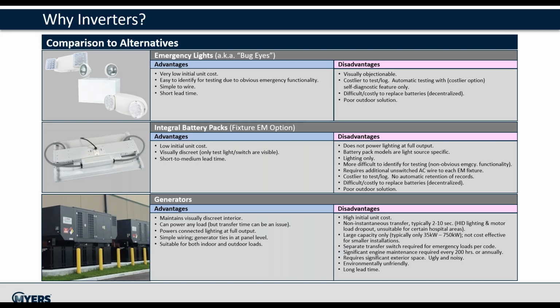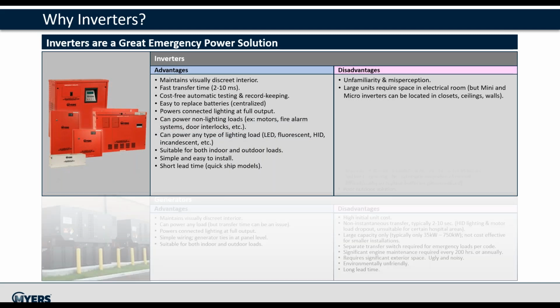Generators' advantages are the interior is visually the same. They power any loads that can accept seconds of interruption, power both indoor and outdoor loads, and have fairly simple wiring. Disadvantages include high initial unit cost and installation. The transfer time is in seconds. They typically come in larger capacities.